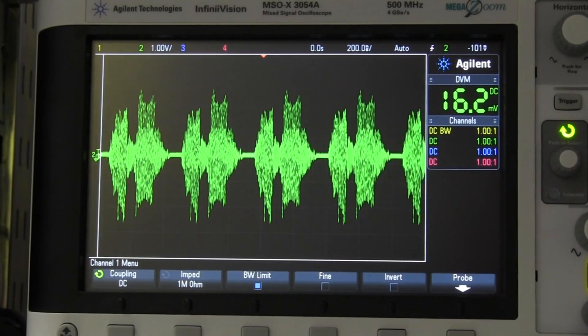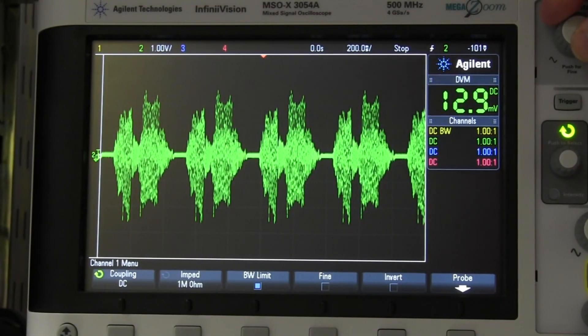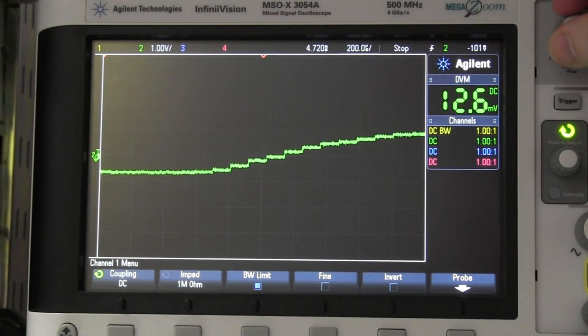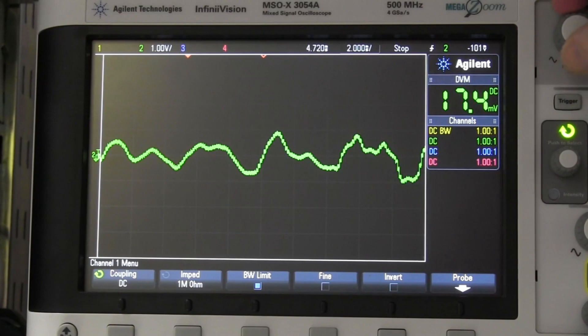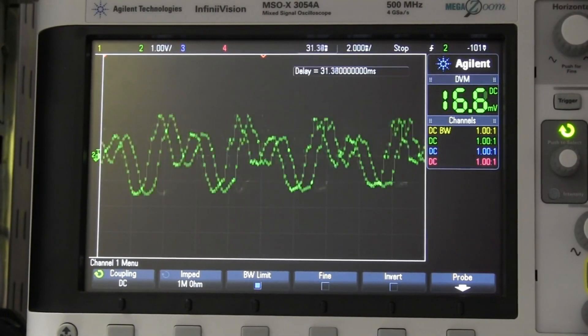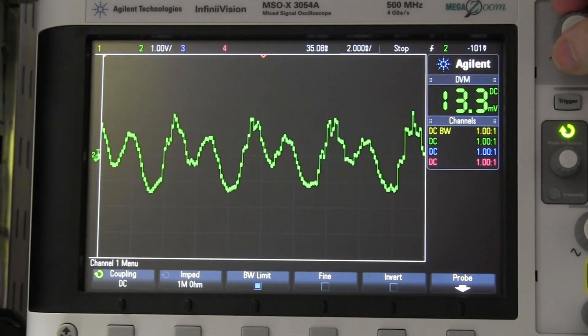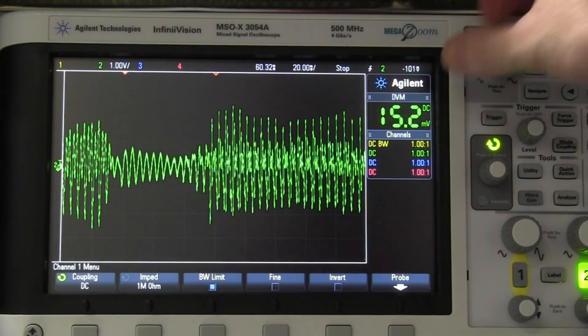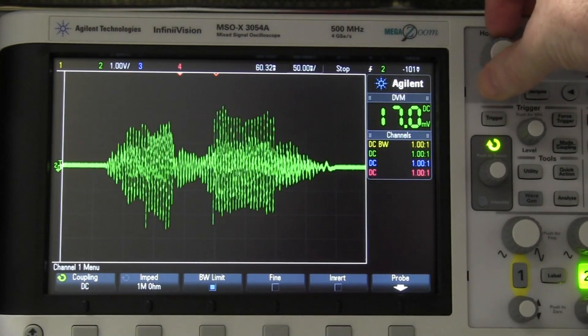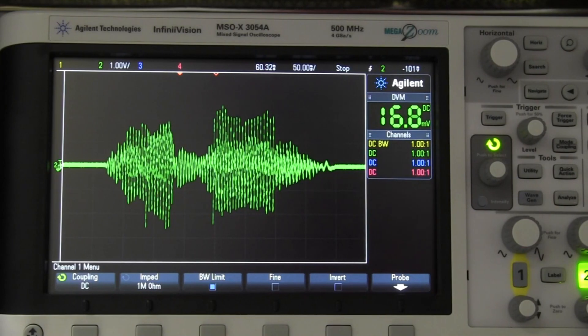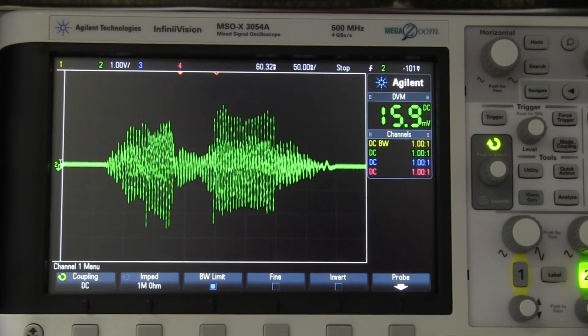And for those who are curious to see the actual waveform, well, we'll single shot capture that, and we'll zoom in, and there, there is your waveform. It's very stepped, of course, it's like it's not even 8-bit, it's very, very coarse. Look at that, extremely coarse, what is that, 6-bits or something. It's pretty terrible, seems like they've just used some crap computer generated voice to generate a crude wave file, and then stick it in there as one of the arbitrary waveforms. They didn't even bother sampling a real human voice in high fidelity, which this thing's capable of, what is it, 14-bits DAC. It's capable of extremely good voice reproduction.